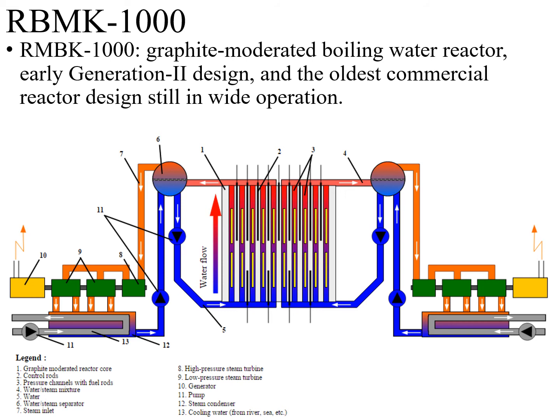This figure shows the basic configuration of this RBMK-1000 reactor. This reactor is specially designed. It is a boiling water reactor because the water is boiled inside the core and produces steam. So this reactor uses multiple fuel channels, and the fuel is located inside each of those fuel channels. Then the steam will be collected inside this water steam separator. Then the dry steam will be sent to the turbine and rotate the generator to produce electricity. Then the wet steam will be condensed inside this condenser. Then the liquid water will be sent back to the core for another boiling cycle.